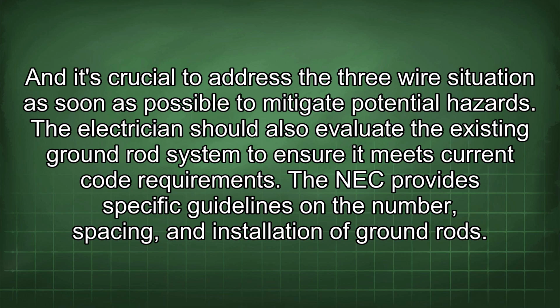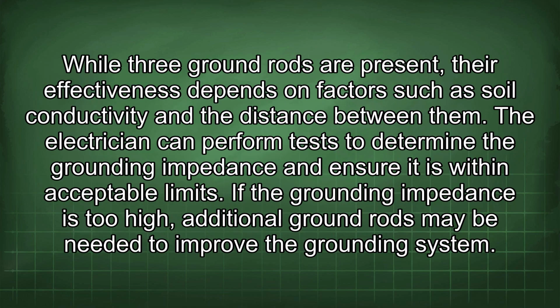The electrician should also evaluate the existing ground rod system to ensure it meets current code requirements. The NEC provides specific guidelines on the number, spacing, and installation of ground rods. While 3 ground rods are present, their effectiveness depends on factors such as soil conductivity and the distance between them. The electrician can perform tests to determine the grounding impedance and ensure it is within acceptable limits. If the grounding impedance is too high, additional ground rods may be needed to improve the grounding system.